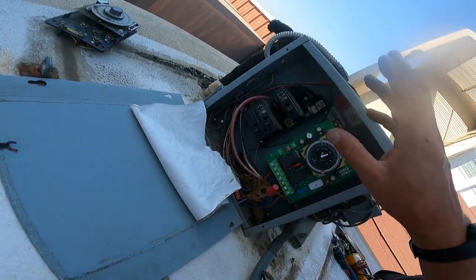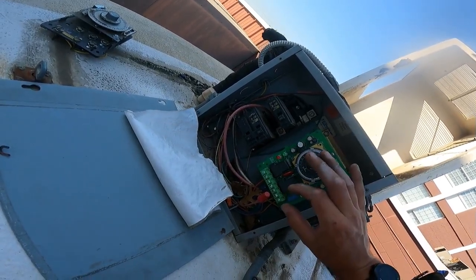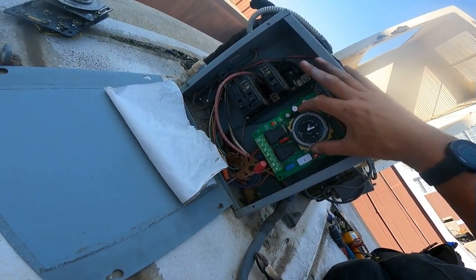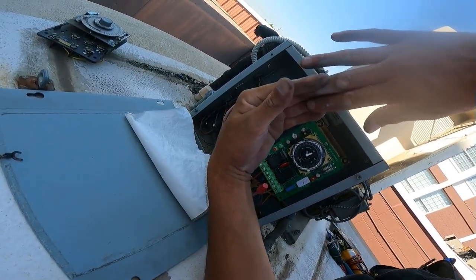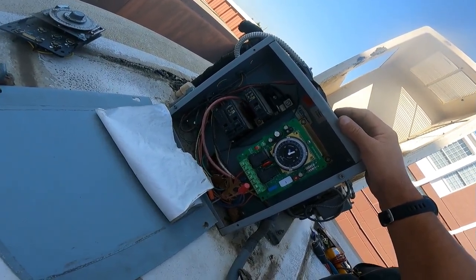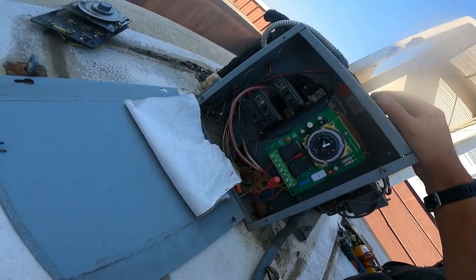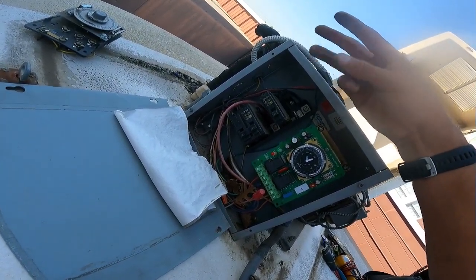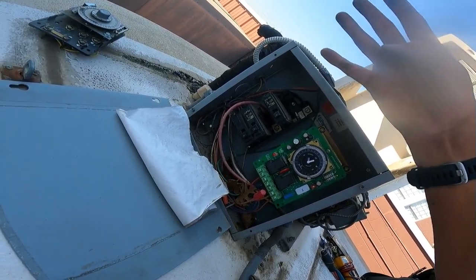And then there's a third type of defrost timer that I've come across. It's mainly in small refrigeration, so it's going to be your reach-ins, and it's going to look just like this. It's only the little time clock. It's got the things that come off the bottom that hook the wires up on, you know. And that one I call a MIL72. I call it that because it starts with MIL72, and then there's some more numbers and crap. I don't know what they mean. I don't care. So MIL72, carry on my truck. DTA V40, I carry 2 of them, and a Paragon, I carry an 814520, one of them on my truck.